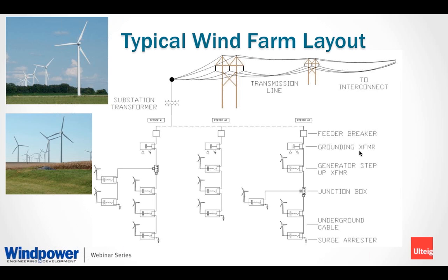Going down a little bit further, you can see the wind turbines are connected to a generator step-up transformer. The generator step-up transformer is a key aspect of where you can save losses too. Depending on the turbine type on which you're installing, these generator step-up transformers are either located up top in the nacelle of the wind turbine tower, or they're located at the base of the wind turbine.